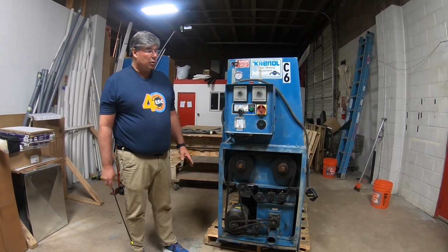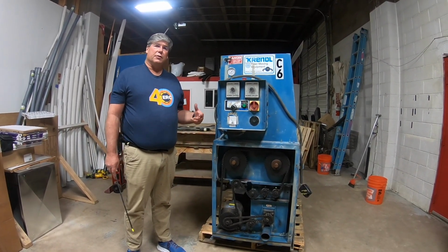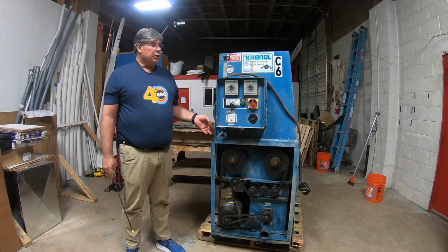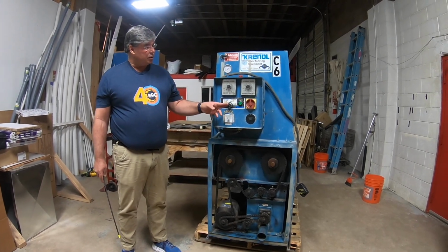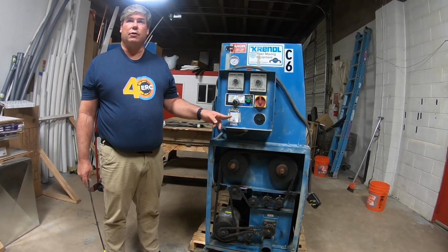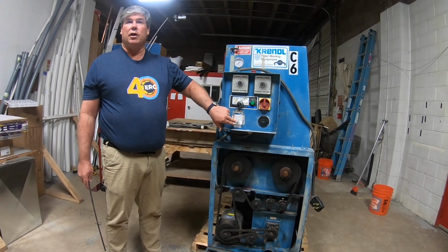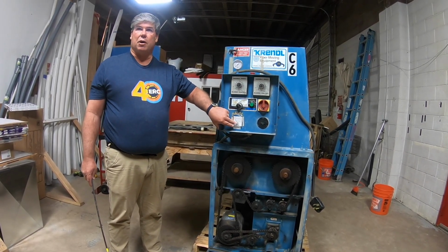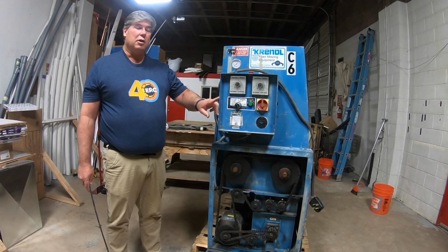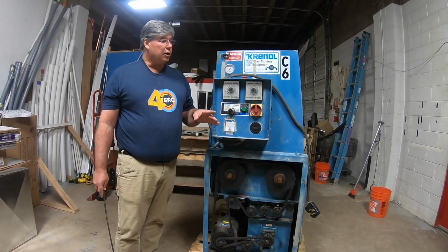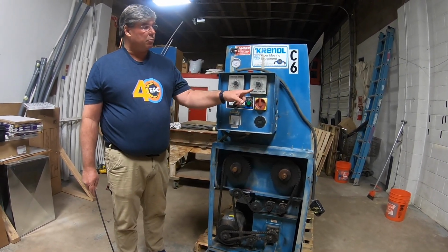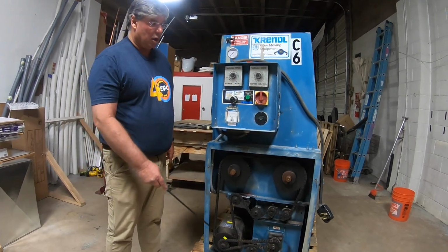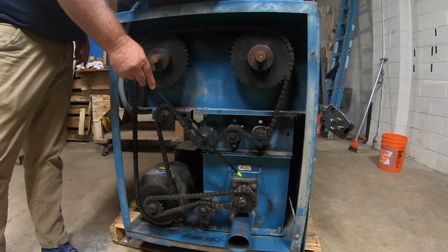One of the things I do on troubleshooting, the first thing I do if they're telling me they're having a problem with equipment is I come and I turn on the voltage, just turn it on, and I'm looking for 240 volts here on the voltmeter. If I'm not showing that, then that tells me my problem's with electricity first. The other thing that we do while we're in this general area is we want to check to see what the blower motors are putting out, as well as what the blower box is doing down here.